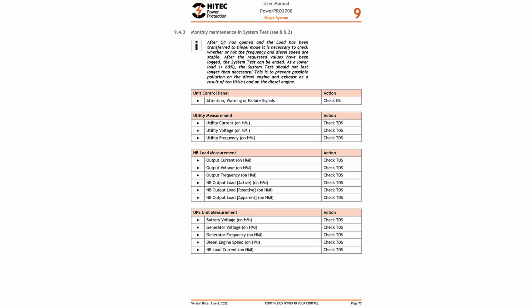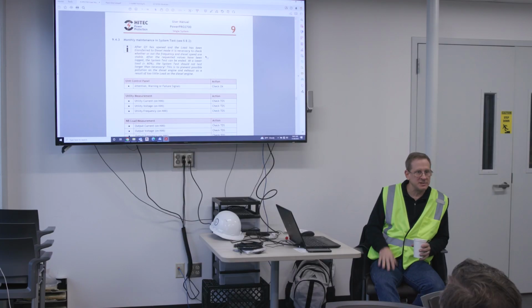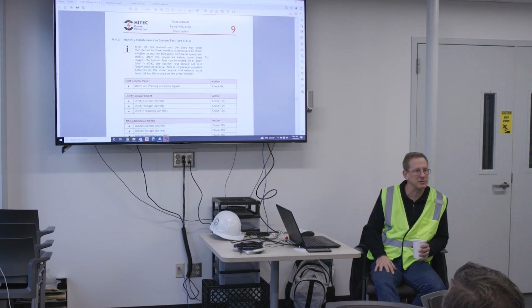Here's a monthly maintenance item where it's recommended that we do a system test every month. At the end of the day that's your decision, but if you run a system test once a month, it confirms not only that the diesel starts but that the flywheel is working correctly and you're able to transition back and forth.